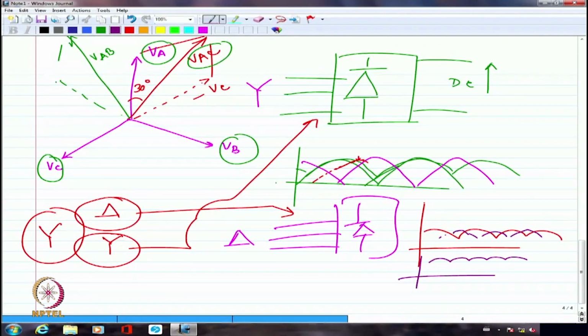So delta-star and star-delta transformers have plenty of applications like this, because they inherently introduce a 30 degree phase shift. That reduces the ripple or variations in the DC voltage by combining two phase-shifted waveforms that are 30 degrees apart.